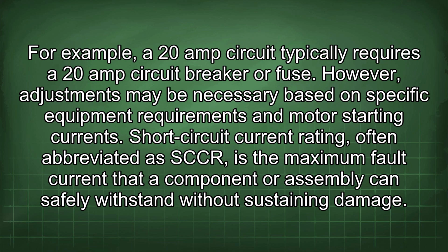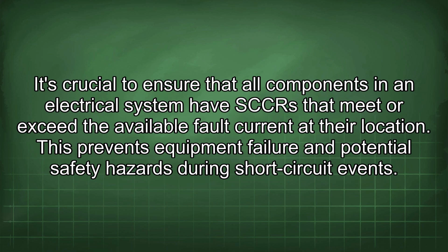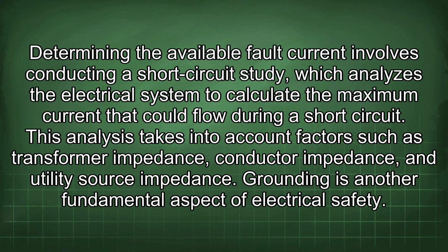Short circuit current rating, often abbreviated as SCCR, is the maximum fault current that a component or assembly can safely withstand without sustaining damage. It's crucial to ensure that all components in an electrical system have SCCRs that meet or exceed the available fault current at their location. This prevents equipment failure and potential safety hazards during short circuit events. Determining the available fault current involves conducting a short circuit study, which analyzes the electrical system to calculate the maximum current that could flow during a short circuit. This analysis takes into account factors such as transformer impedance, conductor impedance, and utility source impedance.